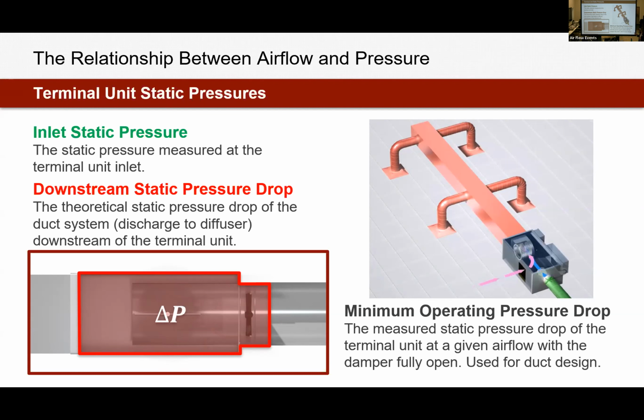The final type of pressure, which is important, is minimum operating pressure drop. You're probably never going to see it actually called that on a schedule or in specs. That is the ASHRAE terminology for the pressure drop of the terminal unit. So down here, we've got the single duct box. The minimum operating pressure drop is just the pressure loss across the terminal unit. I mentioned earlier, we need to be concerned with the pressure drop of all those other accessories. Same thing is true for the terminal unit itself.